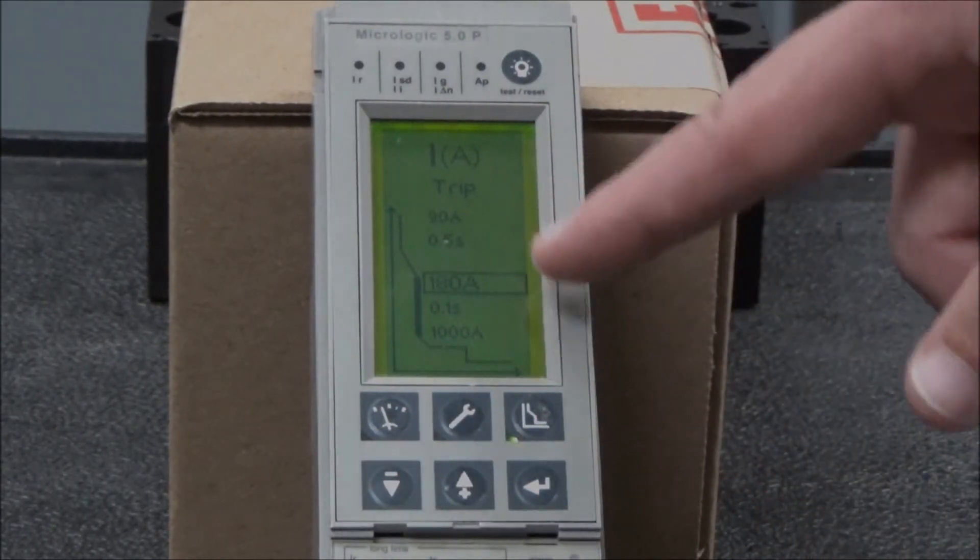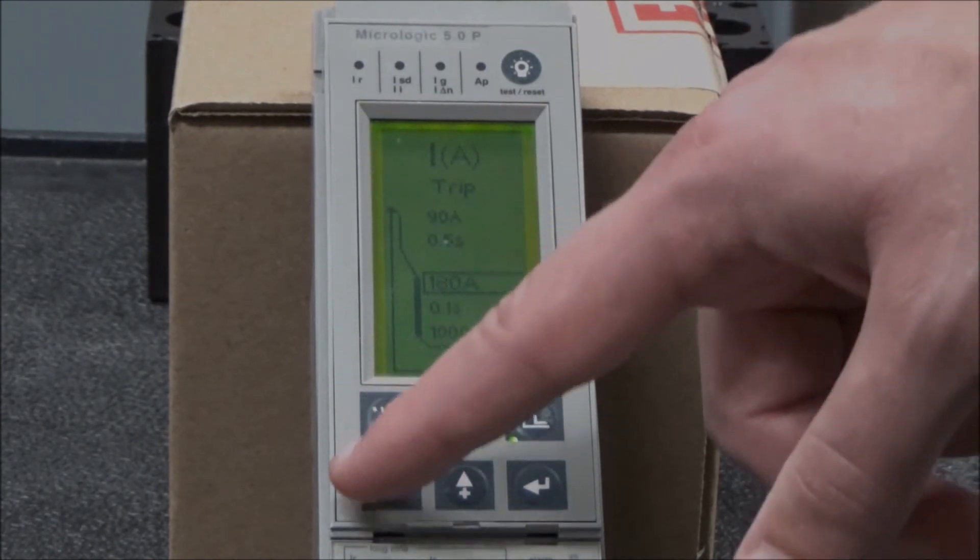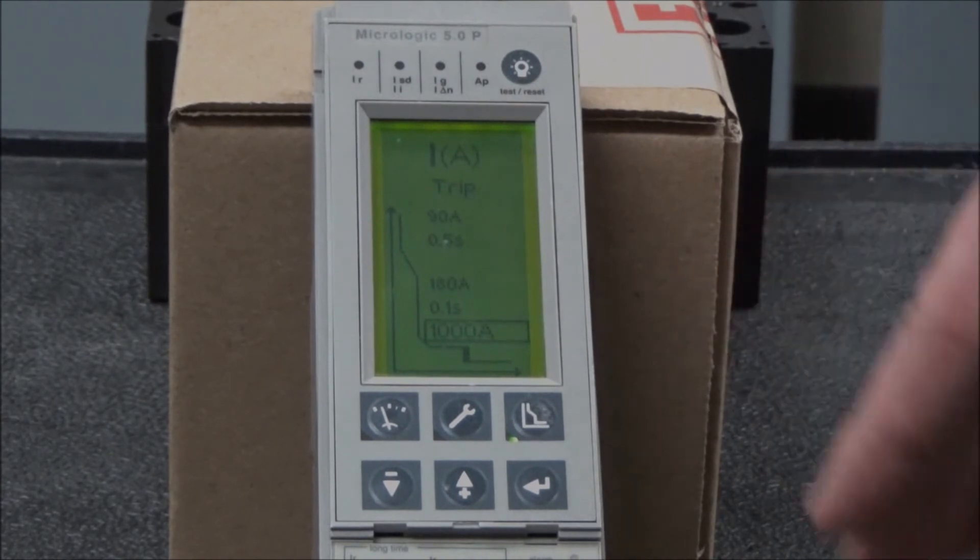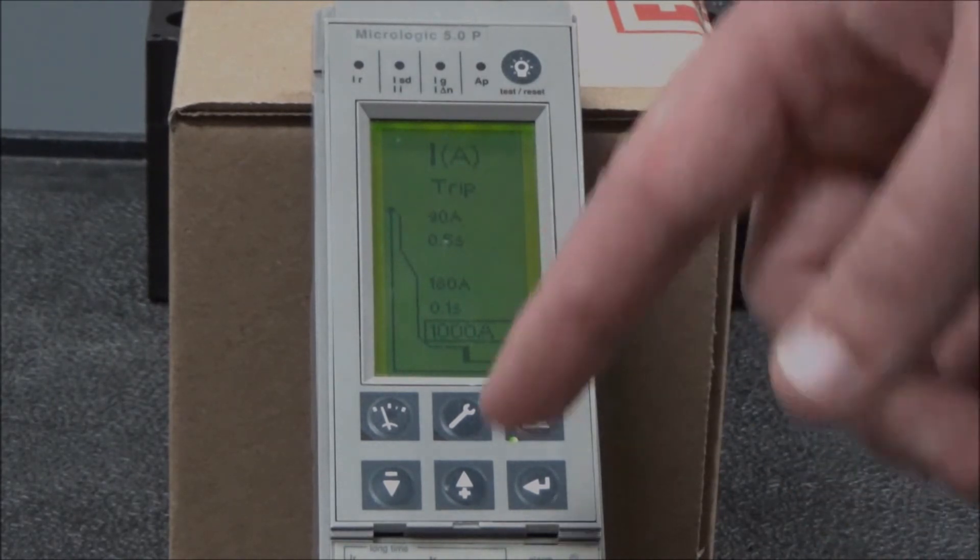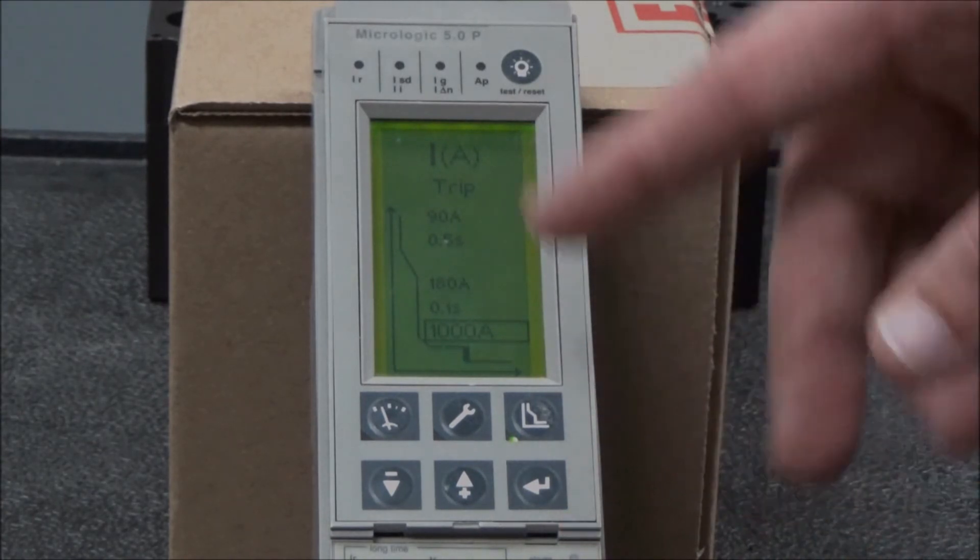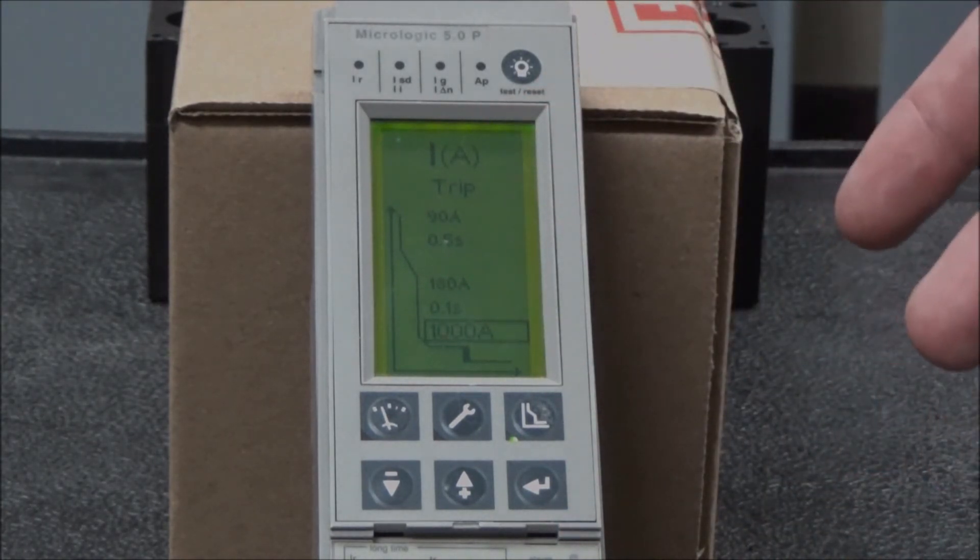The instantaneous and short time settings can be adjusted in 10 amp increments. And the ground fault trip unit settings can be adjusted in 1 amp increments like the long time setting.